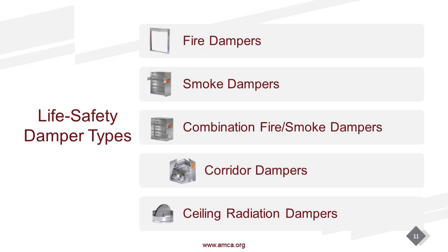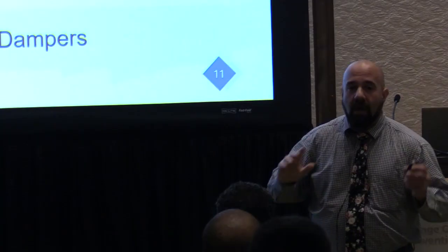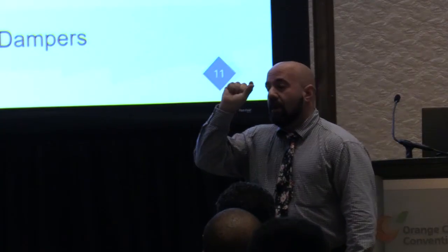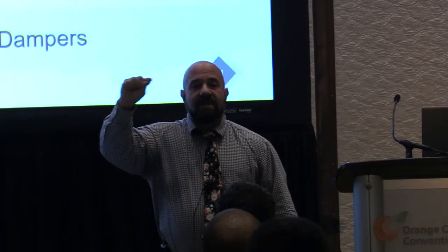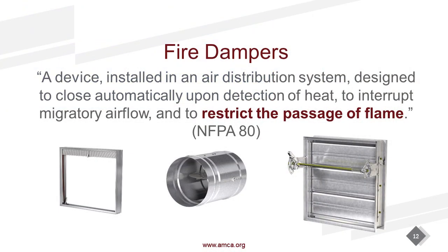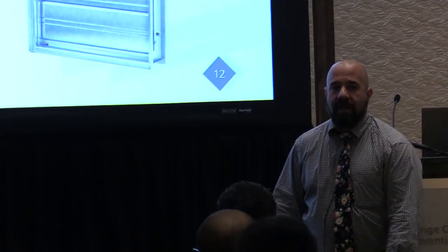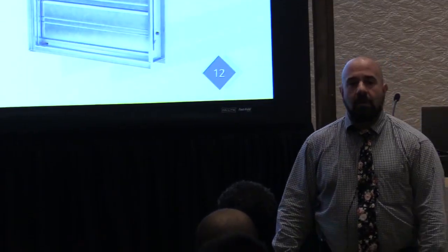But they are specifically tested for installation in a rated ceiling. Now that is not typical for fire dampers and fire smoke dampers. They go in concrete floors usually. But corridor dampers are specifically tested for the framing of corridor ceilings. We'll get into that a little more. Here's your definition of a fire damper. I won't read it to you. It's from NFPA 80. We only care about one thing. We restrict the passage of flame. If this is a fire-rated wall, it is a continuous barrier. I need to get air to the other side of that wall. What do I do? I put a hole in it.